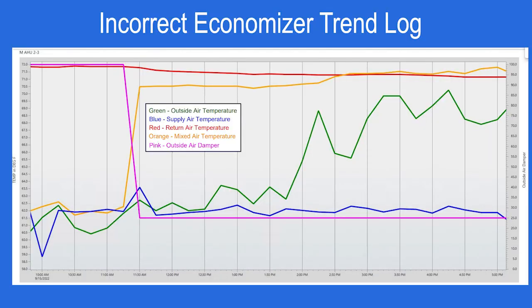And here we have a trend log showing an incorrect economizer function. So you can see here that around 11 a.m. our outside air damper is going to its minimum position, even though our outside air temperature is still well within the range that we could be economizing. It's remaining in the 60s and would be an opportunity for free cooling.